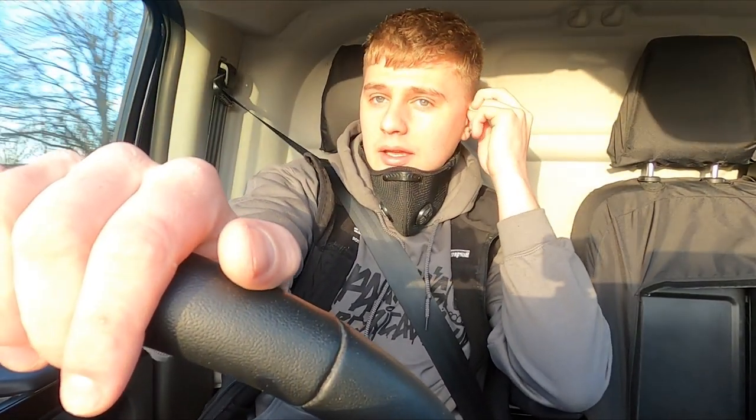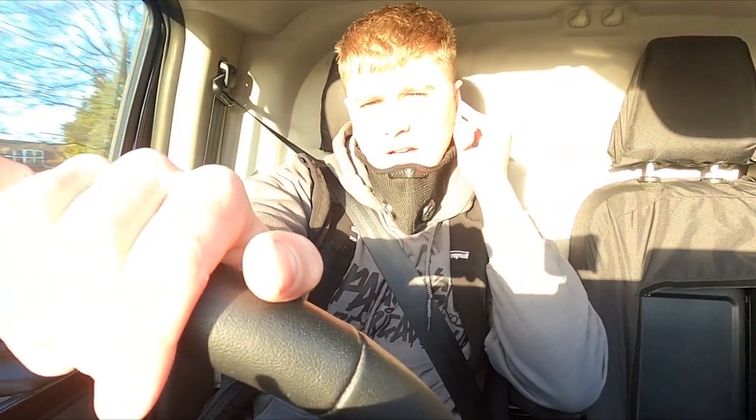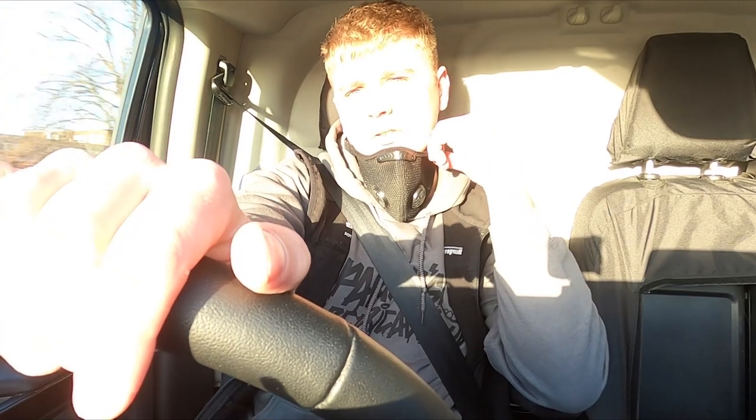Right, so that is me all done and dusted. Just got in the van a lot later than I thought. So when I was testing, I got it all tested, labelled up in the end. One of the circuits ended up feeding another DB in another shed at the bottom of the garden, which no one knew about. And there was like an old pond and stuff, so there's just live ends just in the garden and all that sort of stuff, mad stuff really.